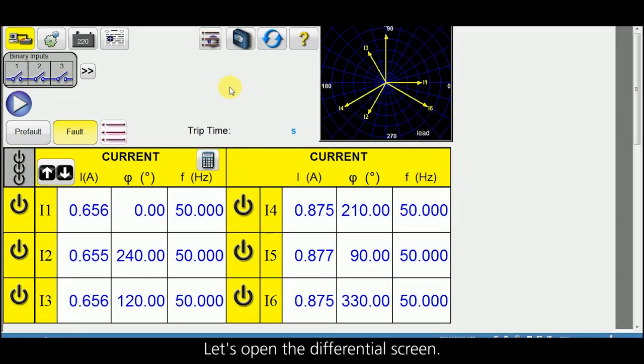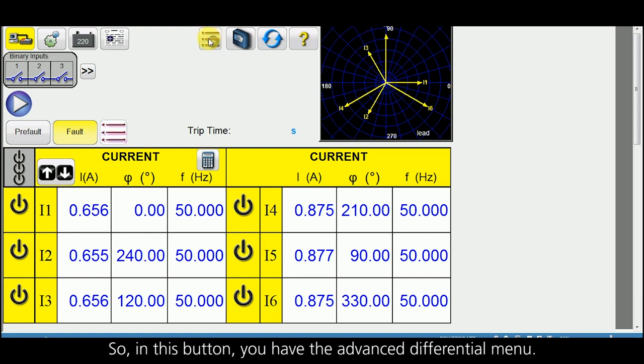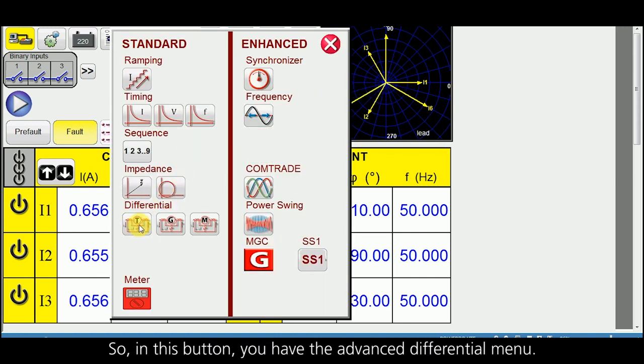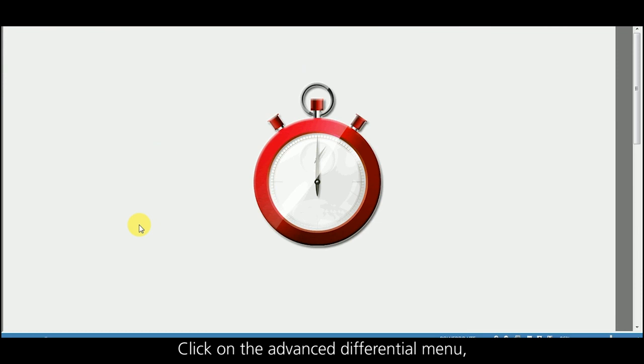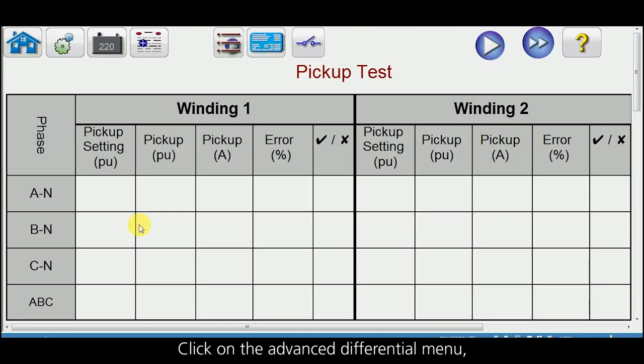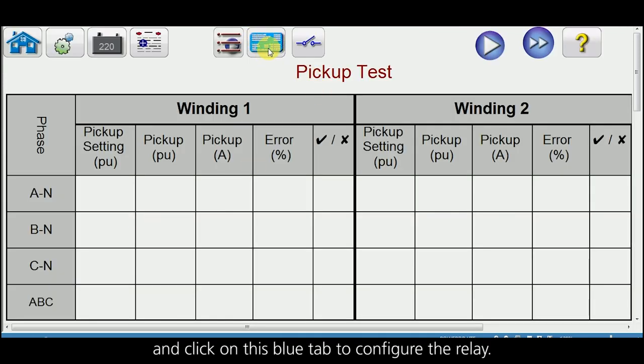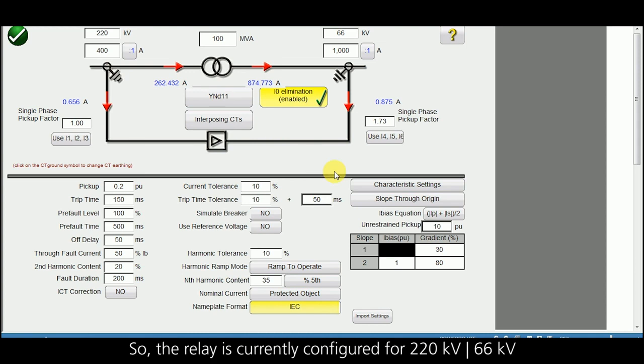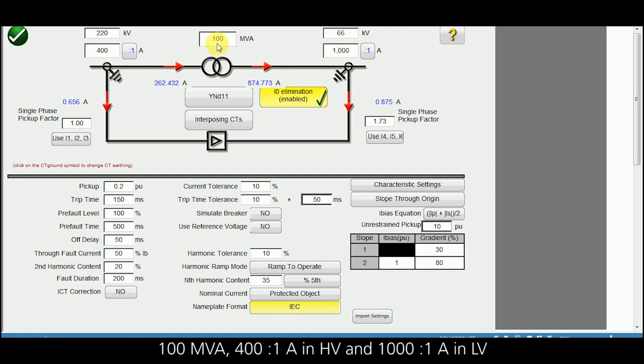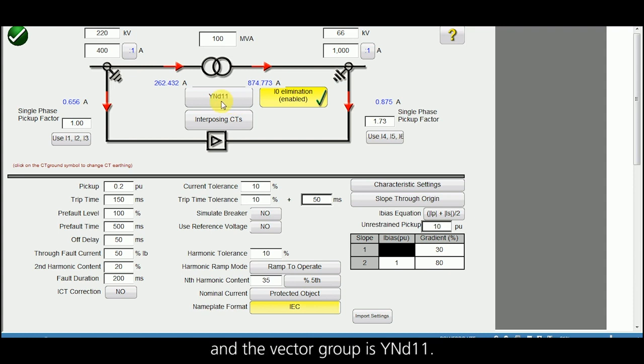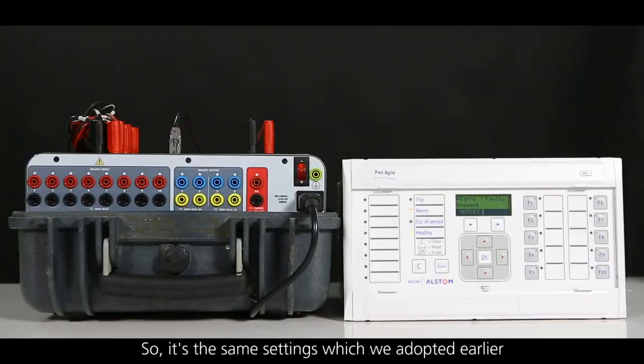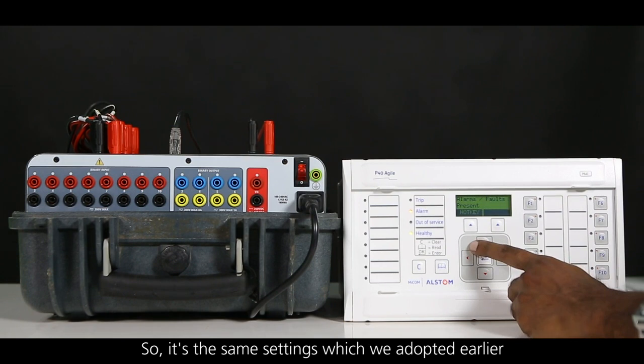Let us open the differential screen. In this button you have the advanced differential menu. Click on the advanced differential menu and click on this blue tab to configure the relay. The relay is currently configured for 220 kV / 66 kV, 100 MVA, 400/1 amp CT in HV, 1000/1 amp CT in LV, and the vector group is YNd11. These are the same settings we adopted earlier.